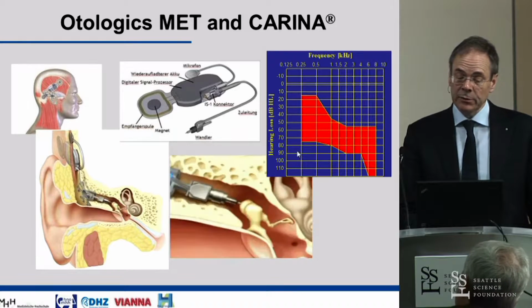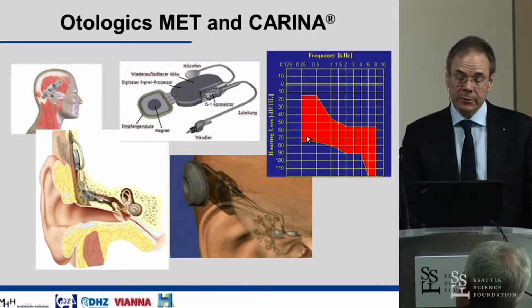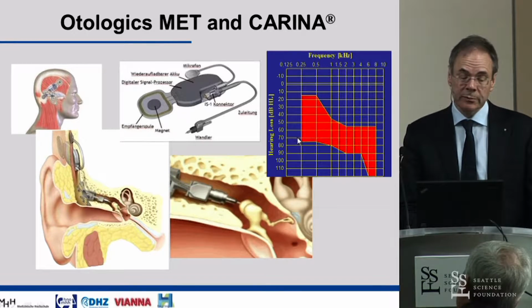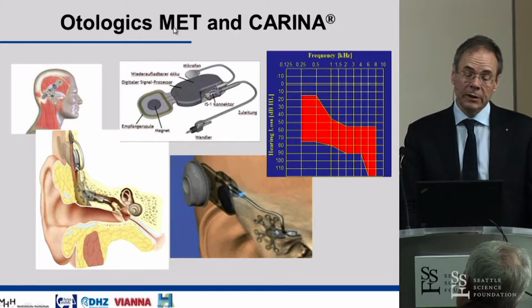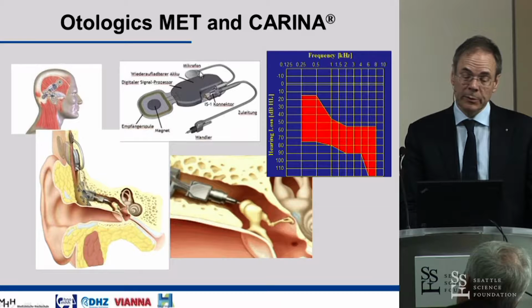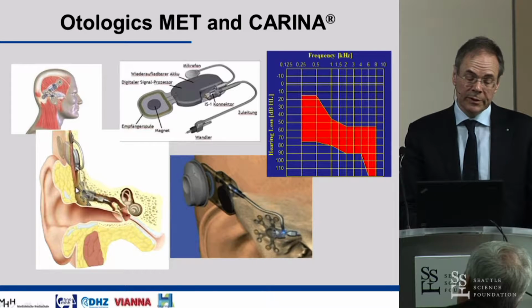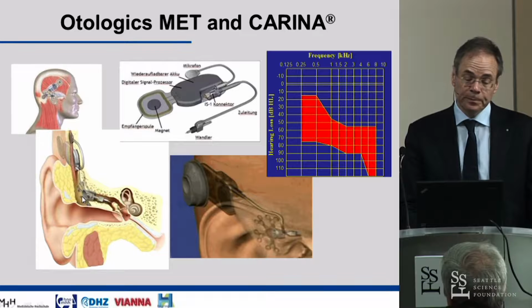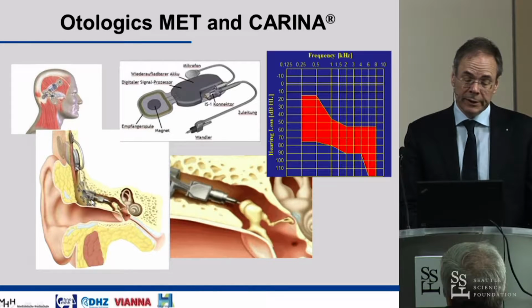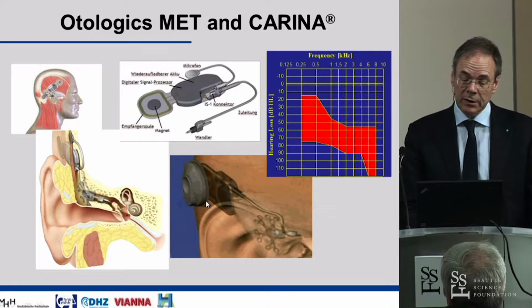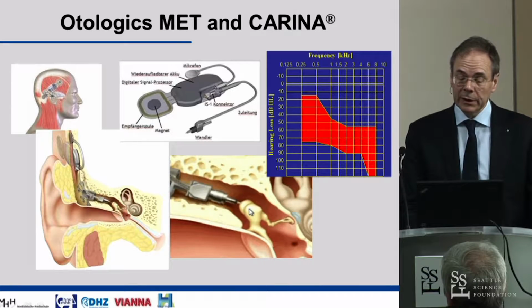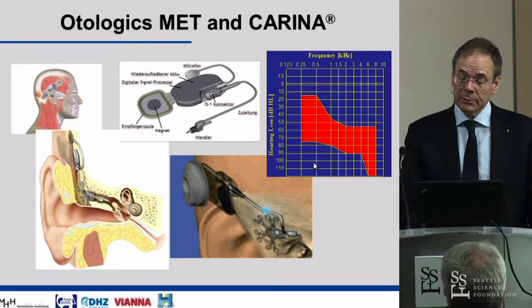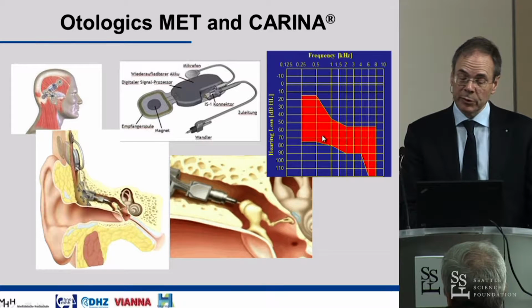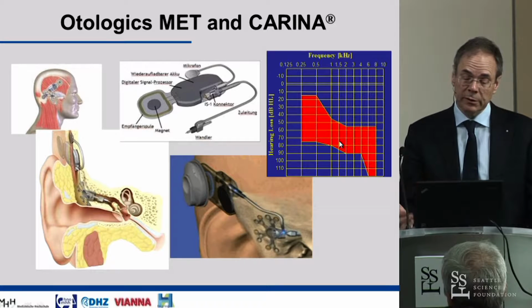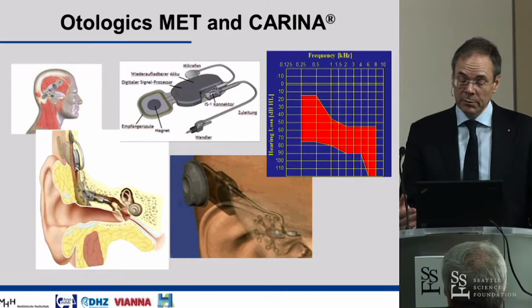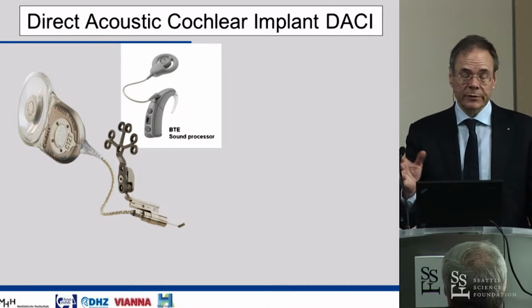Now, as I said, if you have more pronounced hearing loss, then this system is not powerful enough, and you need a 2-point fixation system. Here it's shown the Otologics, or now Cochlear MET middle ear transducer, or the fully implantable version, the CARINA. What it does is basically use the mastoid rim for a fixation with this kind of plating, and then you have the transducer, which goes to the body of the incus. That was the original indication, and then it moves the chain. So you get more gain. You also can serve patients who have a more pronounced inner ear component of their either pure sensorineural or mixed hearing loss. There are also other options to couple, as I have shown before.